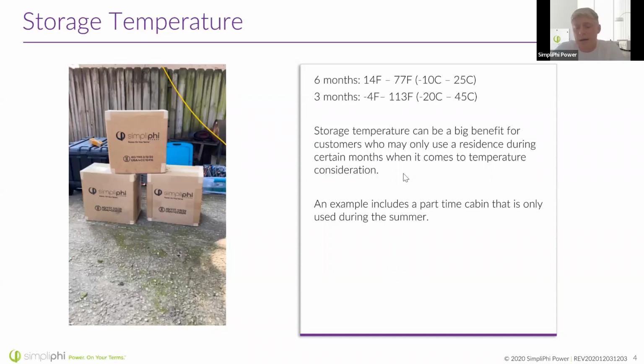Another thing to keep in mind: lead acid batteries in warmer, humid environments will self-discharge and lose energy very quickly, so you'll want to keep those on a float charge. But SimpliPhi batteries really hold their charge well, even in hot and humid environments. So it's a great option for being able to turn these off and decommission a system for a whole season, or even three quarters of the year if you're only visiting your property for a short period each year, maybe in Alaska, and leave everything turned off and decommissioned for the winter. This is actually a common use of our products.